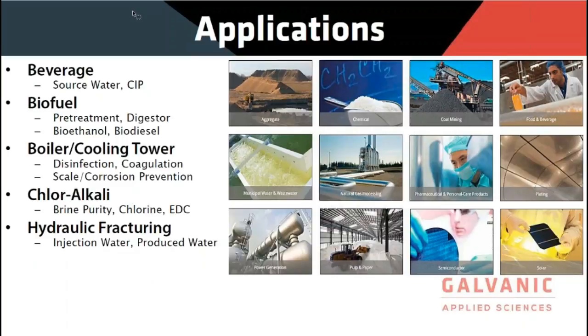Biofuel, so for the pre-treatment stage, digester, bioethanol, biodiesel, they might be looking at the acid and base numbers for product quality. Boiler and cooling tower, so in this case, disinfection, whether it be hydrogen peroxide, chlorine. Coagulation, so monitoring the alkalinity to make sure the pH change isn't too severe, as well as scaling and corrosion prevention. So perhaps looking at sulfite, oxygen scavengers like hydrazine, as well as any scaling from salts, sodium, silica, hardness, etc. Chloralkali has many different applications we can work with.